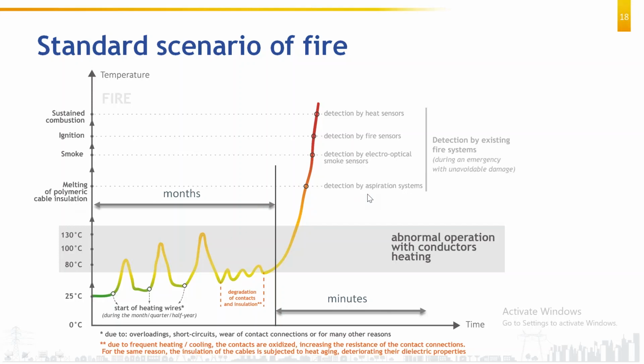At this moment, if you have installed any aspiration system, it will get activated. Then you will have smoke, ignition, and then sustained fire. And if you have an existing fire detection system, it will sense in this particular zone. I will repeat again. When you have a new cable or new equipment, if it is getting overheated beyond the tolerable limits, and if your insulation starts to burn, then you will have smoke, ignition, etc. At this time, your existing fire detection systems will work, not before that.